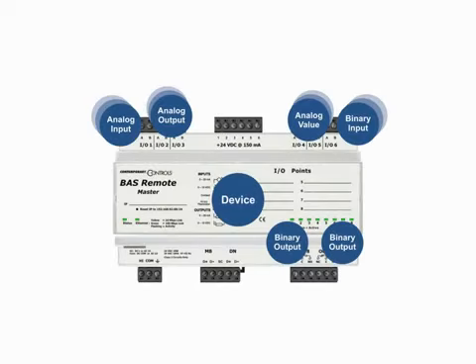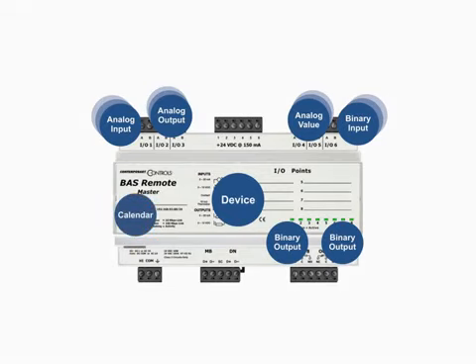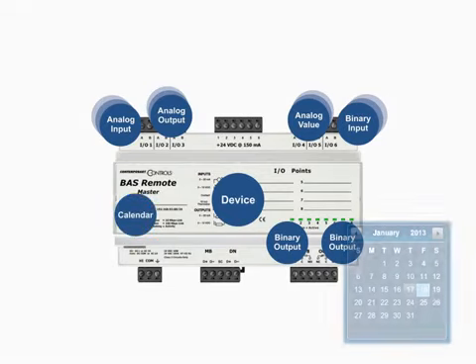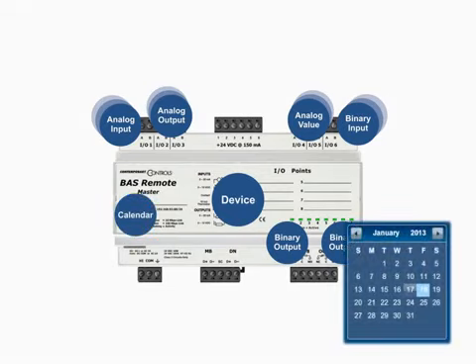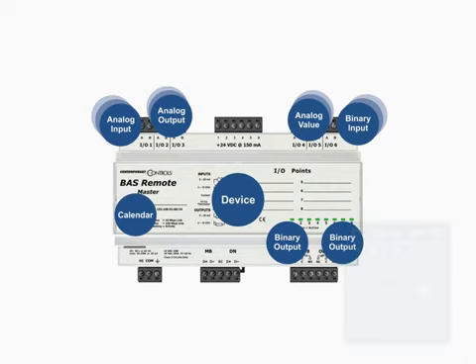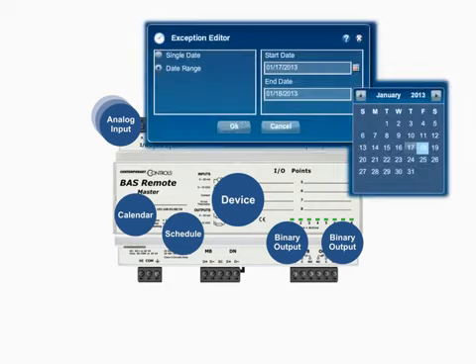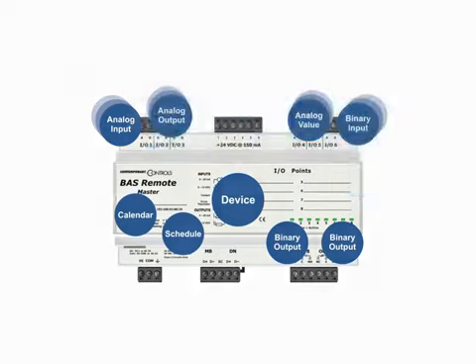The third area is scheduling, where equipment is controlled based upon time and dates residing within BACnet devices. Calendar objects are used to indicate whether each day is active or inactive according to that calendar. Schedule objects are based upon time-value pairs that specify a value to use at a particular time. Schedules can have exceptions to accommodate holidays.